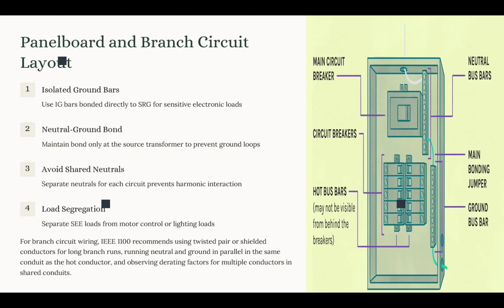Okay. Another one is neutral to ground bonding. We need to maintain the neutral to ground bond only at the source transformer. This way, we prevent parallel neutral ground paths, so we avoid circulating current or having common mode noise. We have to avoid sharing the neutrals in the panel. So we have to provide a separate neutral conductor for each of the branches in our panel. Okay, this is very important because nonlinear loads generate triplen harmonics, like third harmonic, ninth harmonic, 15th harmonic. And if we have a shared neutral, they do not cancel in the neutral and basically add up arithmetically.